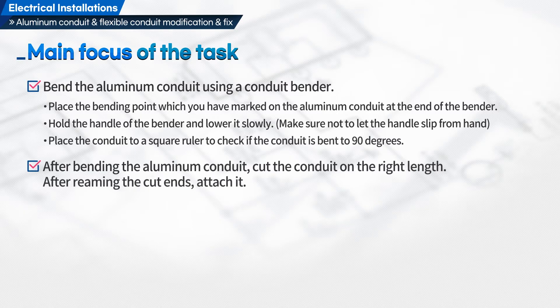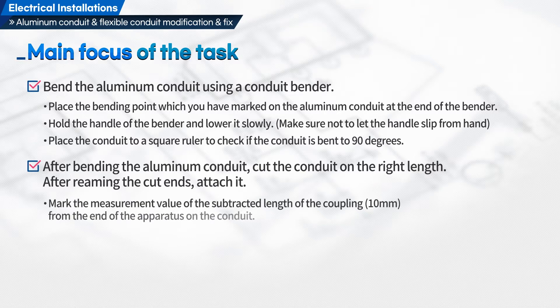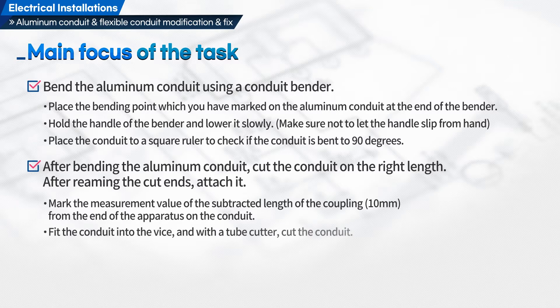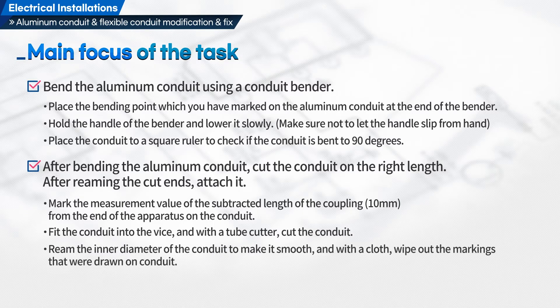Fourth, after bending the aluminum conduit, cut the conduit to the right length. After reaming the cut ends, attach it. Mark the measurement value of the subtracted length of the coupling — 10 mm — from the end of the apparatus on the conduit. Fit the conduit into the vise and with a tube cutter, cut the conduit. Ream the inner diameter of the conduit to make it smooth, then wipe out the markings drawn on the conduit with a cloth.